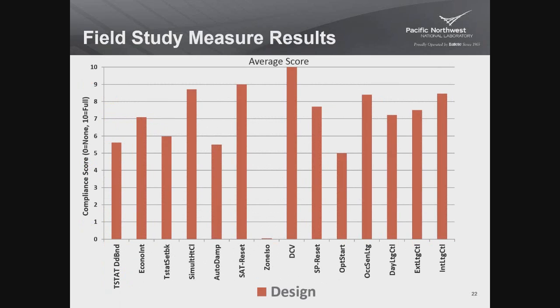So now on to some results. This is for the design perspective for each of the 14 requirements. And you can see there's a really broad range. For demand control ventilation, in all the buildings where this control requirement was triggered, and not every requirement was triggered in every building. For example, the ones that deal with VAV reheat systems are only triggered in buildings that have VAV reheat systems, obviously. But demand control ventilation, which was triggered in a lot of buildings, was always included in the design.